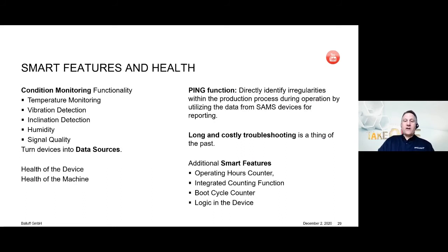Also, we're talking about additional functionality. There's a ping function in every device, just like when your computer is on a network, and it helps to identify irregularities in communication, or where the device is and whether it is communicating, and have that reported. Then there are additional smart features such as operating hours at the port level on a master block or a hub, integrated counting, boot cycle, and logic built into the device, which I'll talk about in a second. All of this adds up to helping reduce the cost and time of troubleshooting, and again, really being able to implement predictive maintenance.